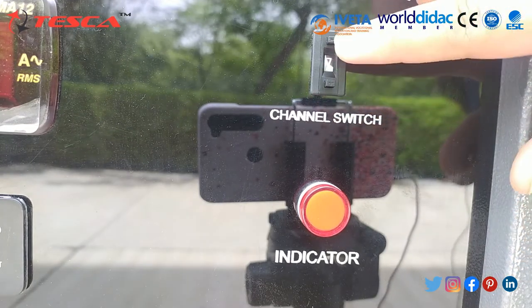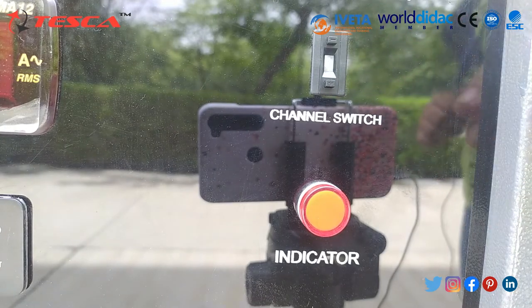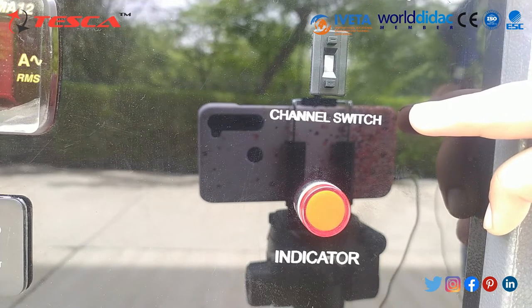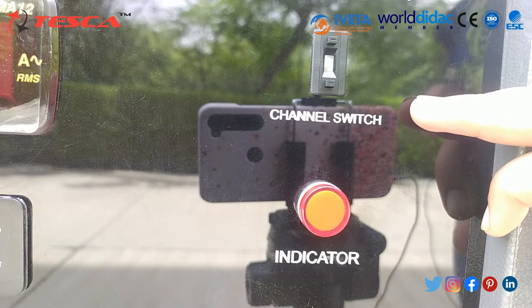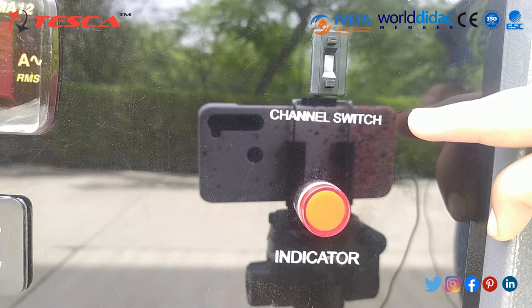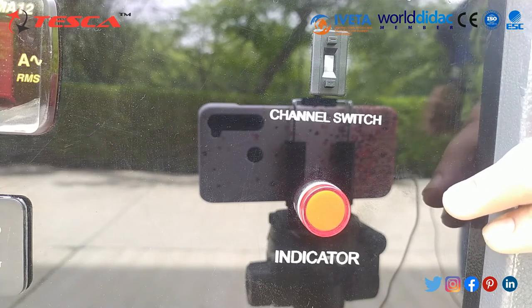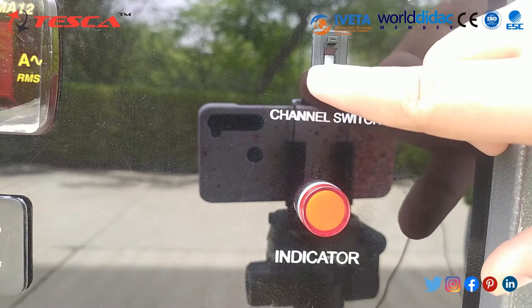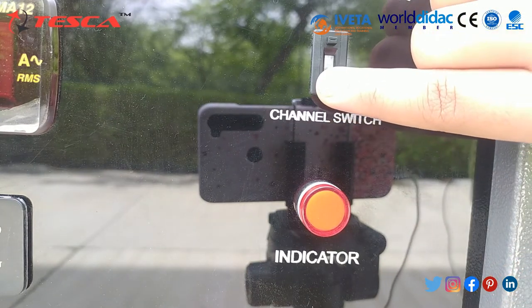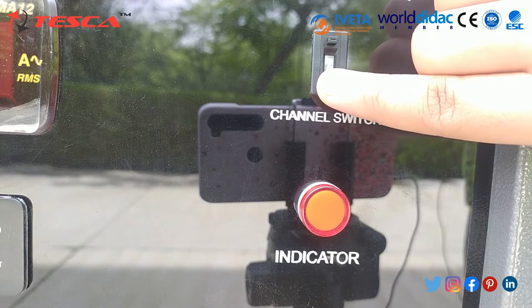There is a channel switch and a temperature indicator. Through the channel switch you can select different modes. T1 indicates the compressor inlet for gas; T2 indicates the compressor outlet or condenser inlet for gas; T3 indicates the condenser outlet or capillary inlet for gas; T4 indicates the capillary outlet or evaporator inlet; T5 indicates the water inlet; T6 indicates the water outlet from the condenser; and T7 indicates the water outlet from the evaporator.